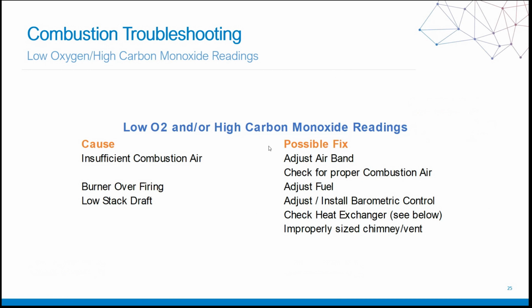Is the system misbehaving? Is the orifice improperly sized? So we want to check whether we have a burner that is overfiring. Another issue that can create low oxygen or high carbon monoxide is low stack draft. In this case, as I talked about when we discussed draft, we want to adjust or install a barometric controller or barometric damper, so we check and evaluate, or install one, to make sure that we have proper stack draft. Do we have a cracked heat exchanger that is letting more air into our combustion process and thus affecting the way that the byproducts of combustion are drafting or leaving?